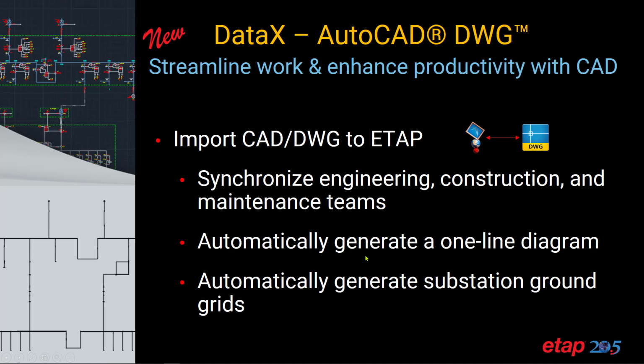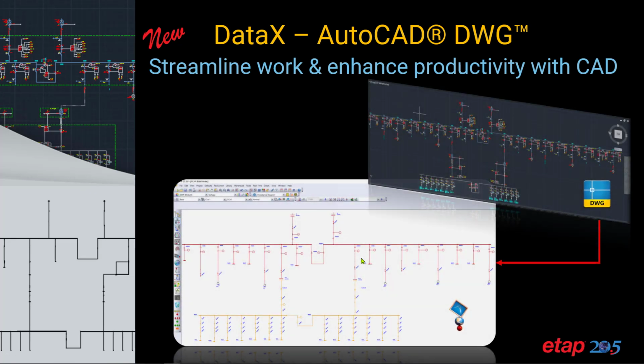We can automatically generate a one-line diagram once we read the AutoCAD file, and you can also use it to automatically generate the substation ground grids. The AutoCAD file that is read by ETAP is then converted, including the connectivity, into the ETAP model.